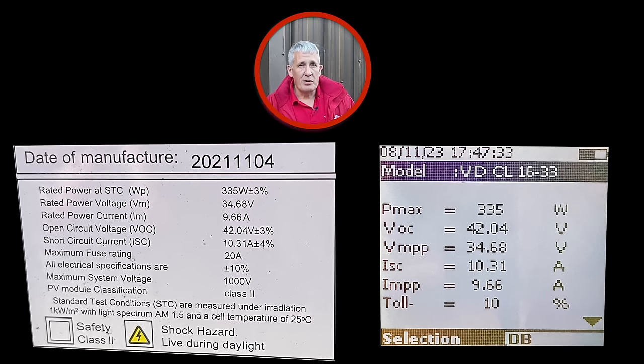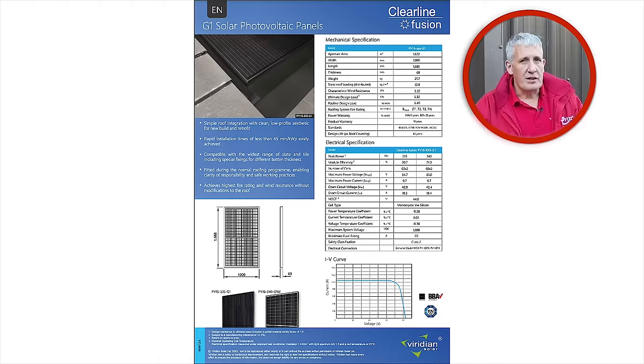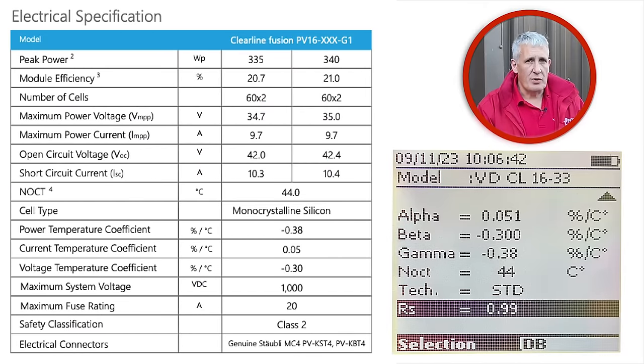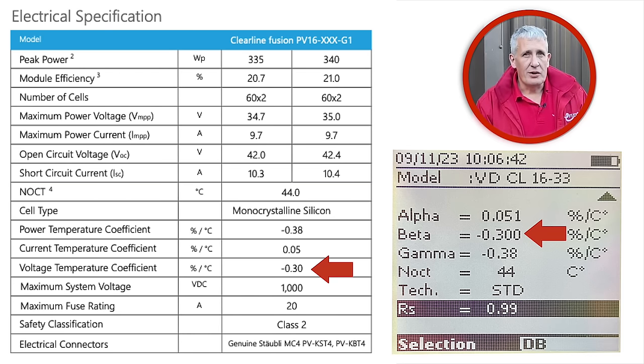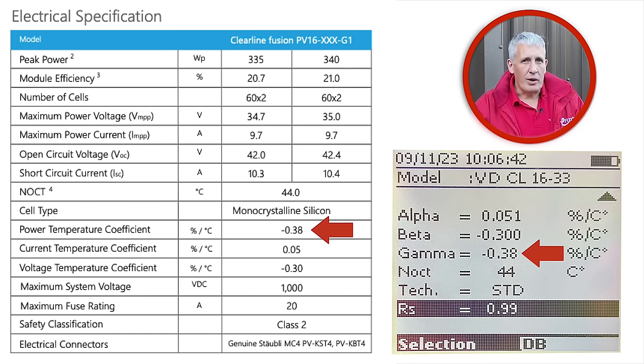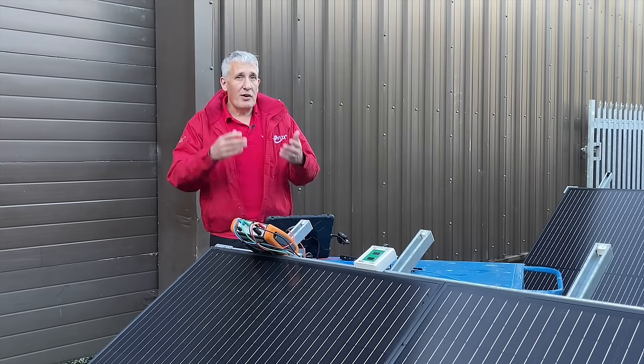Let's enter the data from the rating plate. The maximum power for these modules is 335 watts, so I'm going to enter that along with open circuit voltage, voltage and current when operating at maximum power, and the short circuit current. We also need to include the specified tolerance values of plus or minus 10%. The next three values are found on the datasheet: the temperature coefficients, in other words how the values change with temperature. Alpha is the change in short circuit current, beta is the change in open circuit voltage, and gamma is the change in power, all in degrees Celsius. NOCT is the Normal Operating Cell Temperature — 44°C in this case. We're using Standard Test Conditions and RS is the series resistance of the panels.